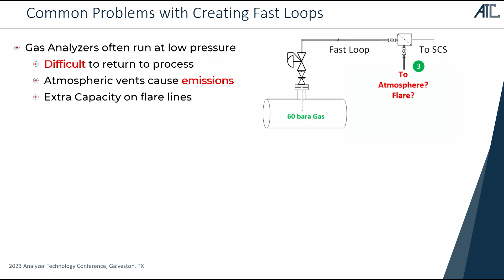And then yet another place where we often don't put a fast loop in, but we really need one, is near vaporizers. If we're putting a liquid vaporizer in near the sample tap, we would really like to have a fast loop in front of it, because vaporizers take very, very low liquid flow rates. If you look at a vaporizer that's running about 1 liter a minute of gas on the gas phase side, it might only be vaporizing 2 or 3 milliliters a minute of liquids. And since time is volume divided by flow rate, if we have very low flow rates on the inlet to the vaporizer, we can have very long time delays.